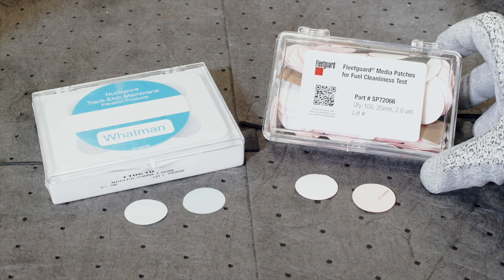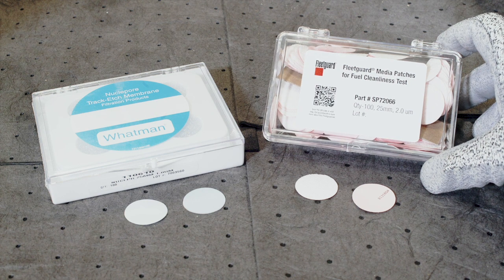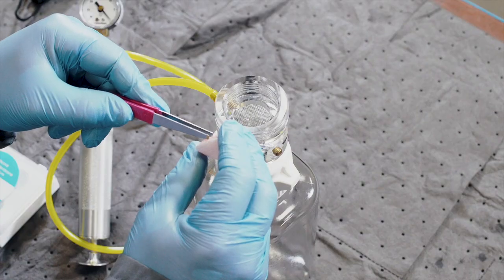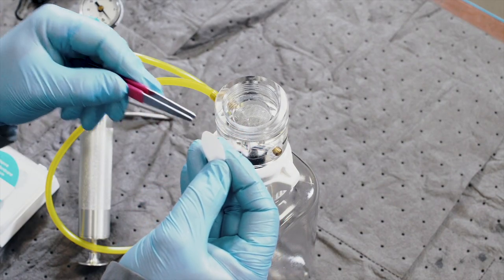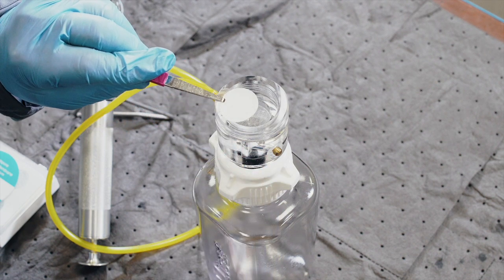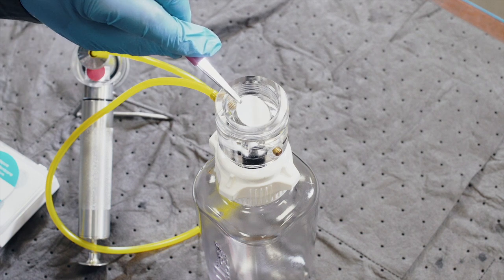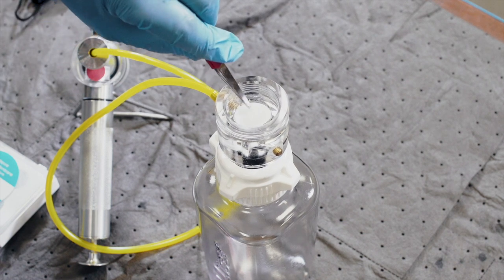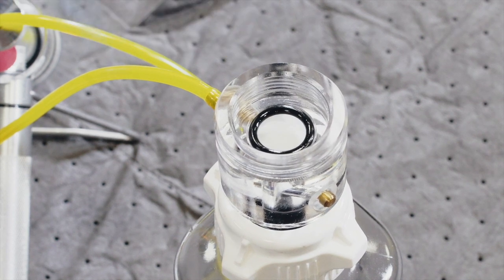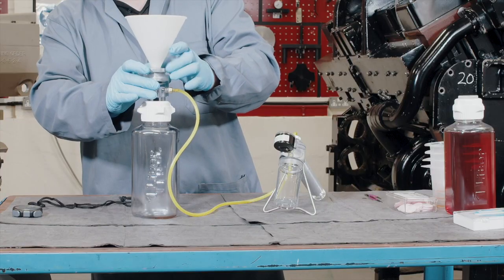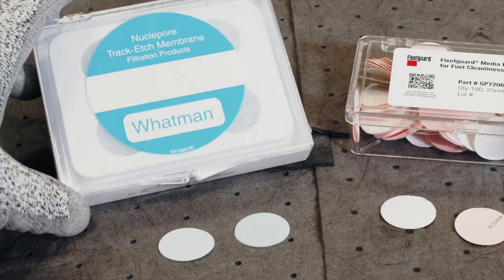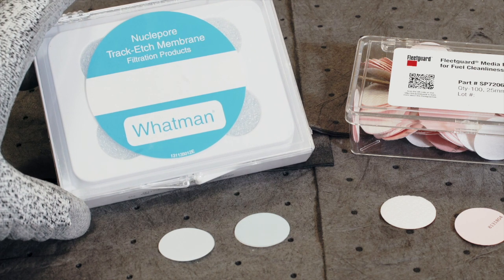For this test you can use either the two micron or one micron patch, and only one patch is required for the entire test. Remove any coloured cover or separated sheets from the media and then carefully place the media with the grooved side facing the metal screen. Fit the small diameter o-ring on top of the filter media and then tighten the funnel securely in place. If using the one micron media, ensure that the shiny side is facing up.